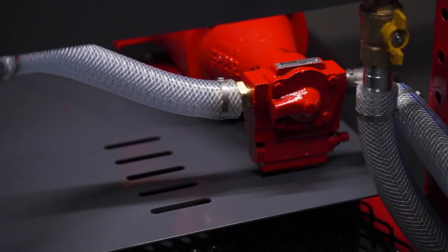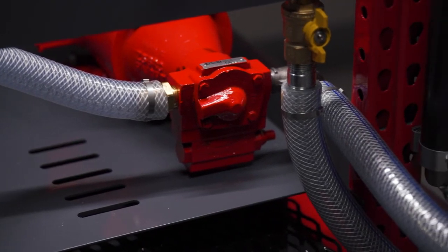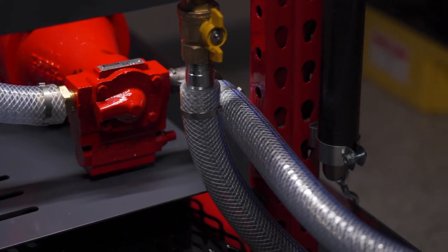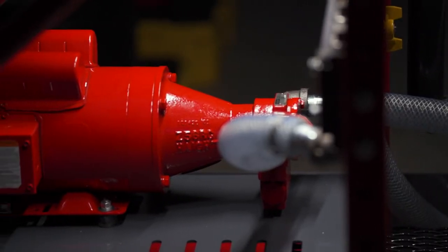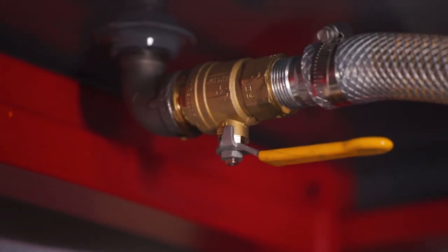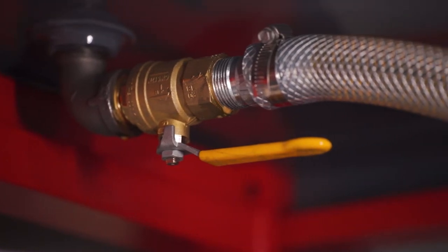The bronze gear pump is a rugged, self-priming, positive displacement pump and can handle viscosities up to an ISO 680 without a problem. The pump flow rates are from 2.5 to 4.5 gallons per minute, depending on the oil viscosity. The Performance System contains robust brass shut-off ball valves.